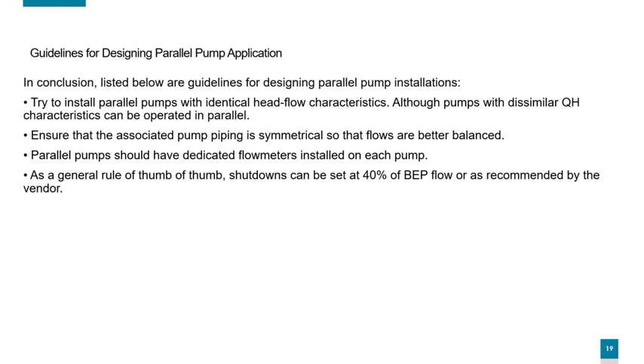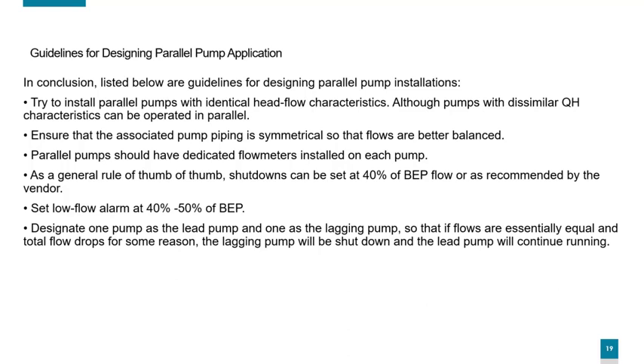As a general rule of thumb, shutdowns can be set at 40% of best efficiency point flow or as recommended by the vendor. Set low flow alarm at 40 to 50%, say 50%, of best efficiency point. Designate one pump as the lead pump and one as the lagging pump, so that if flows are essentially equal and total flow drops for some reason, the lagging pump will be shut down and the lead pump will continue running.